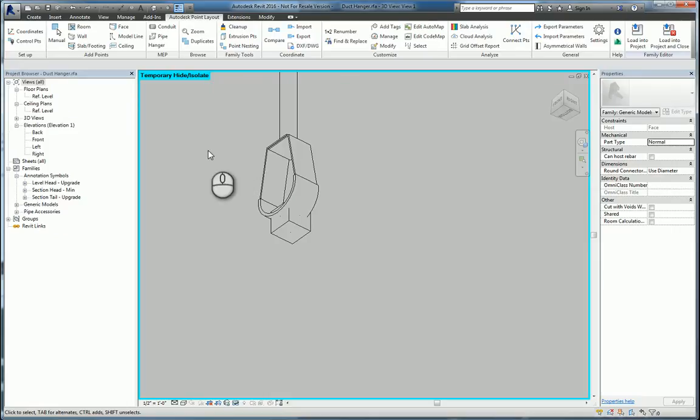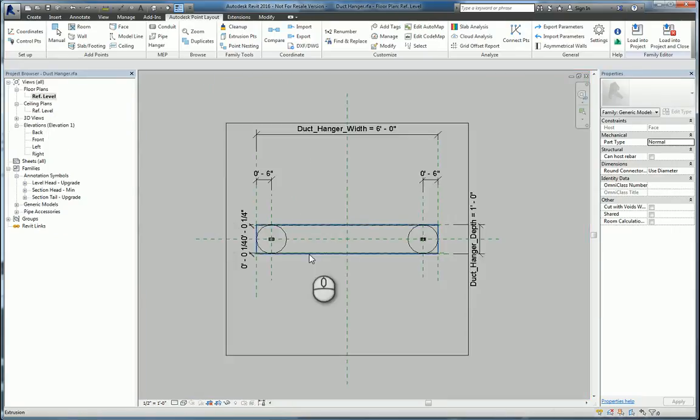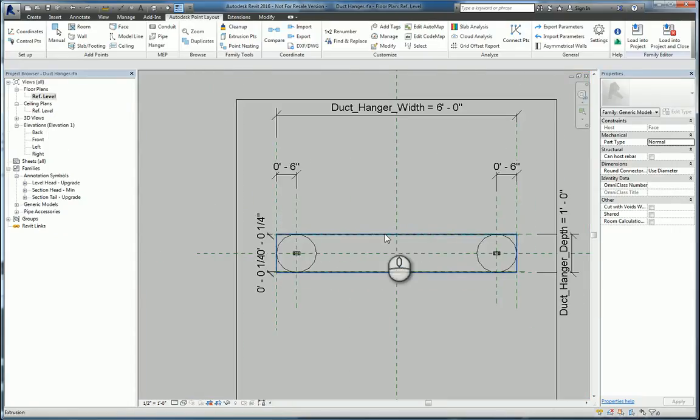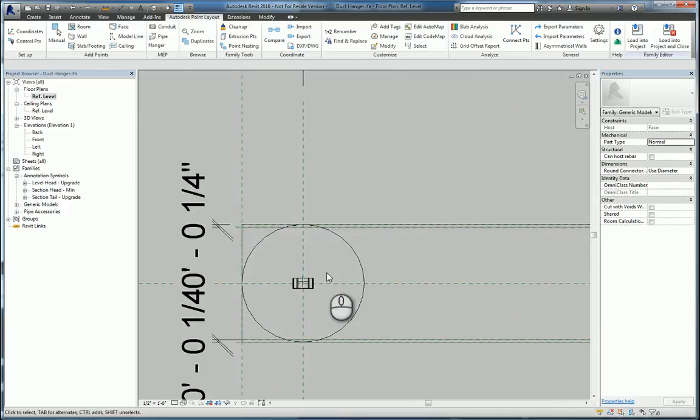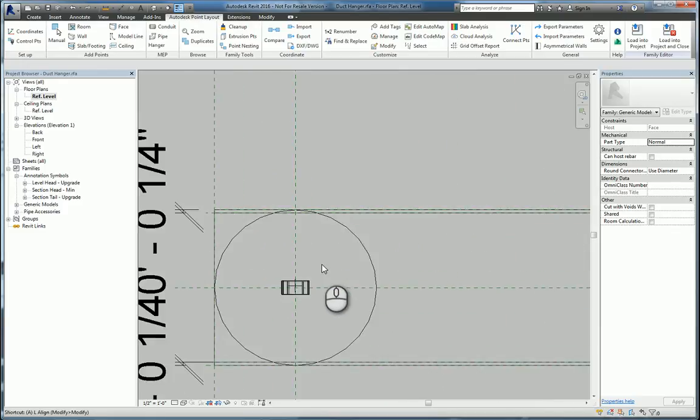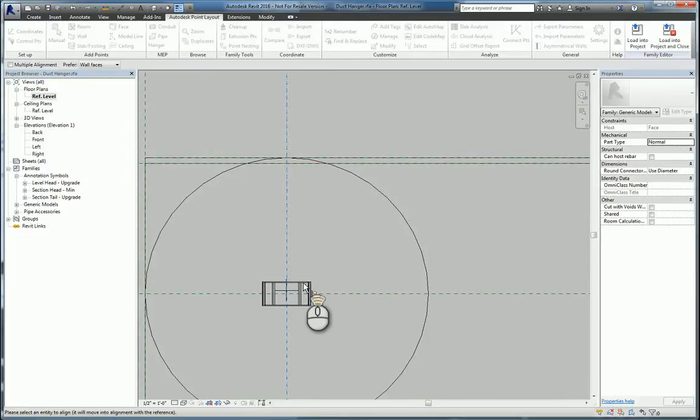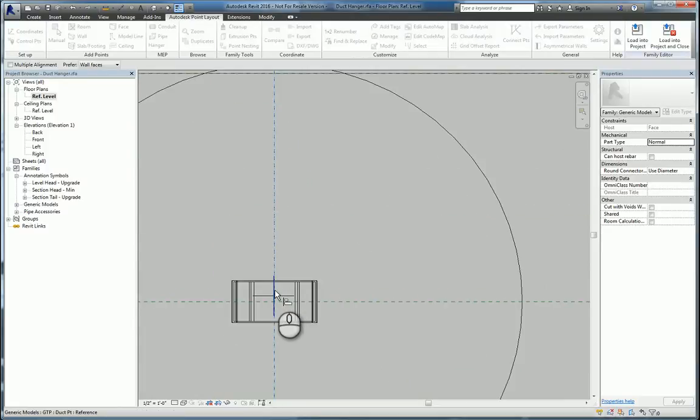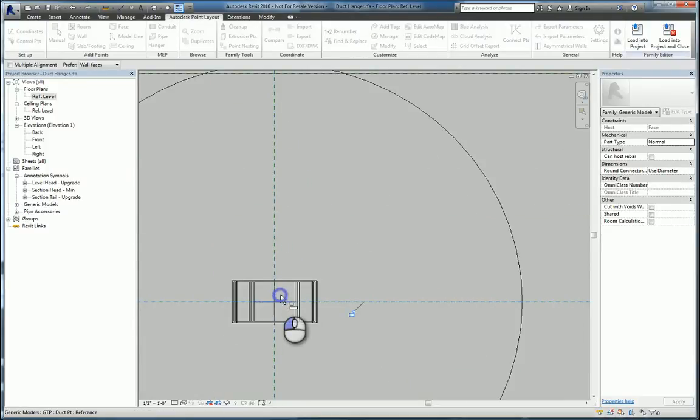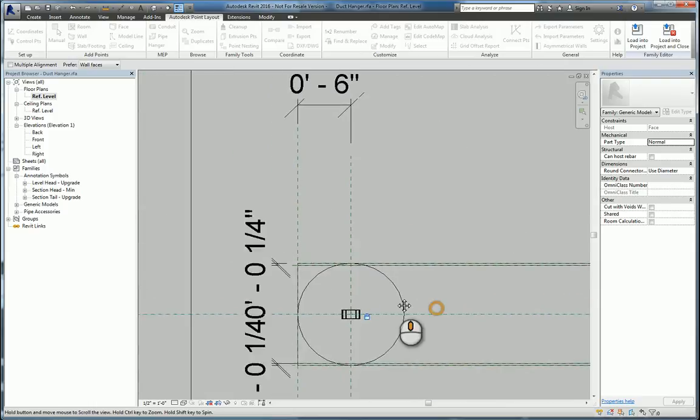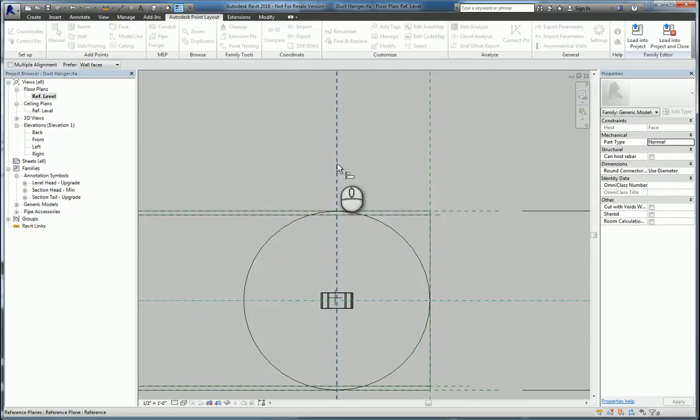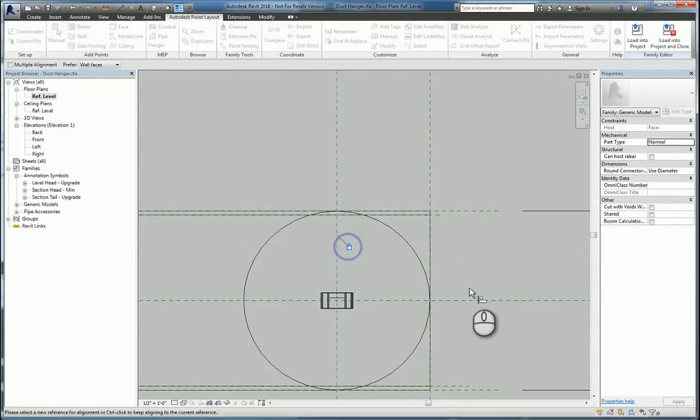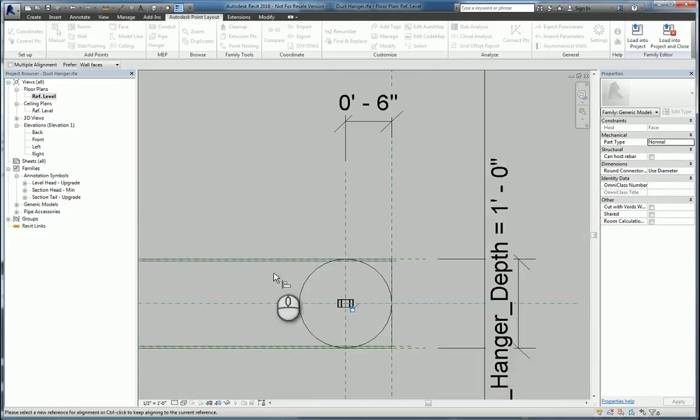Now that we have it placed, we need to make sure that it's aligned and locked properly to the reference planes, because our duct hanger width changes, and our depth may change as well. So we can use the Align command to align to those reference planes that control point, both in vertical and horizontal positioning on both of them.